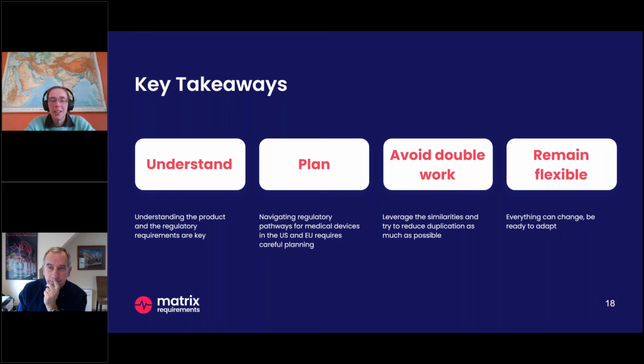When it comes to being compliant with MDD and MDR requirements, the MDD also says that you need to comply with state of the art. My suggestion would be to go for newer versions of standards if they have been released. That was also already a bit the case before. When you're focusing on US and EU markets, the harmonized standards in Europe tended to be behind in versioning compared to what is recognized in the US. If you have to choose, go for the highest version of the standard. There will not come harmonized standards to a lower version of a standard than what is published at the moment.